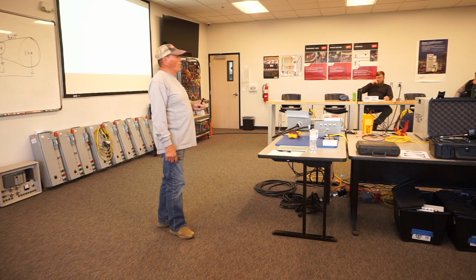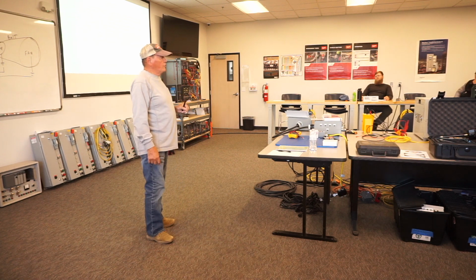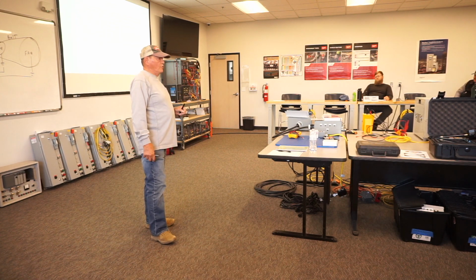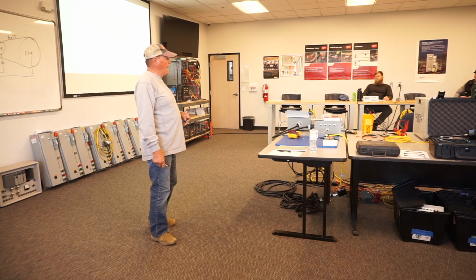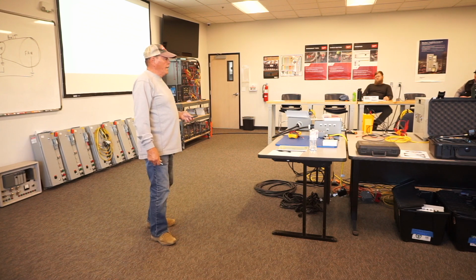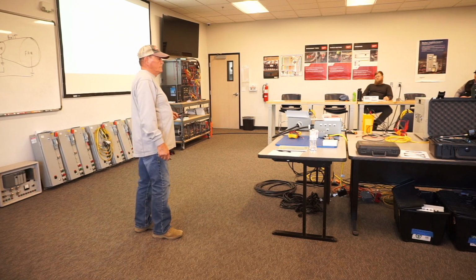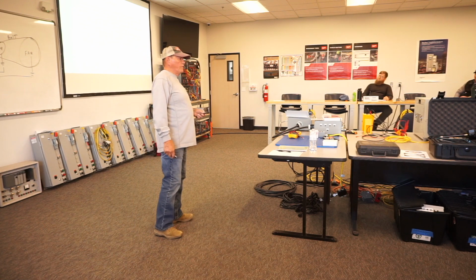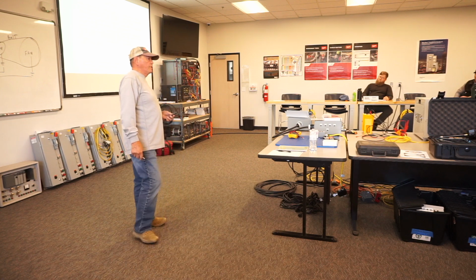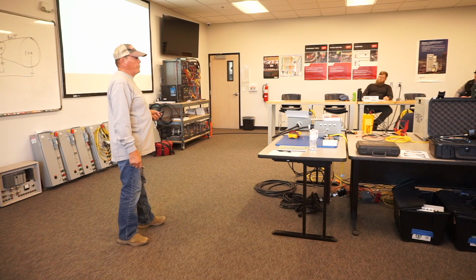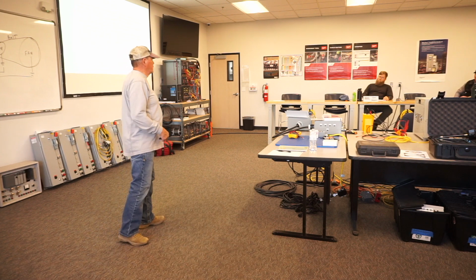So, therefore, building wire sucks for grounding purposes because we're dealing with high frequency. And if we're dealing with high frequency, a building wire becomes an open circuit or a high impedance path to provide a path for high frequency, ground faults, anything that travels at high frequency, which coming off a drive is exactly where we're in.